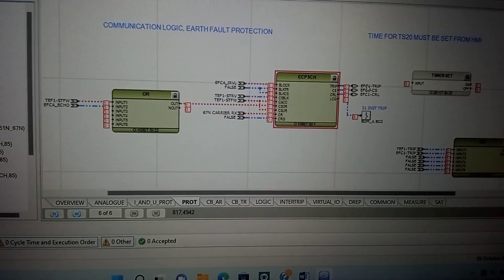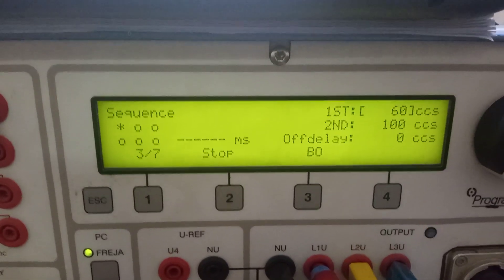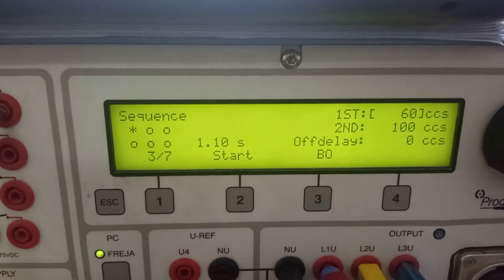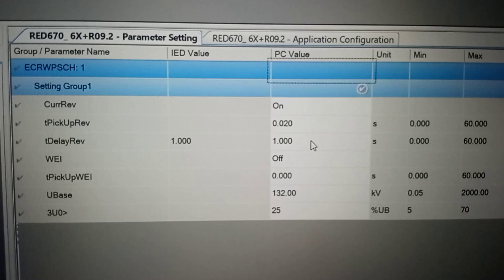It is all changing now — you can see in the red line. Same here also for timing — you can verify the timing now. Our setting is one second. After one second with the fault present, it will trip.